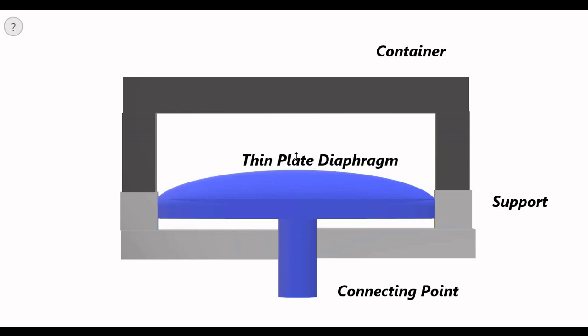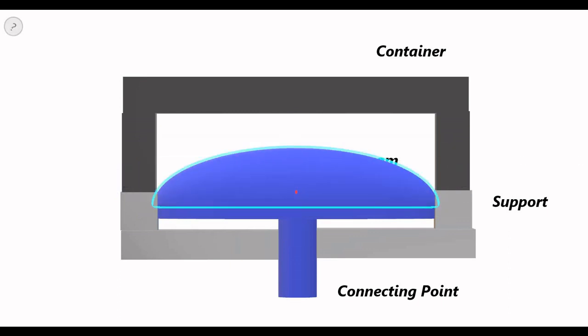Through the formula which we established, the axial displacement, here happening along the y-axis, from the tip of the diaphragm to the reference position, establishes a relationship between the axial displacement from the bottom tip to the top tip of the diaphragm and the differential pressure, that is, the pressure inside the diaphragm and the pressure outside the diaphragm, which is connected to the liquid column and the atmospheric pressure combined. So we measure the axial displacement from the tip of the diaphragm to the original reference position, happening along the y-axis. This is the basic principle of liquid level measurement using thin plate diaphragms.